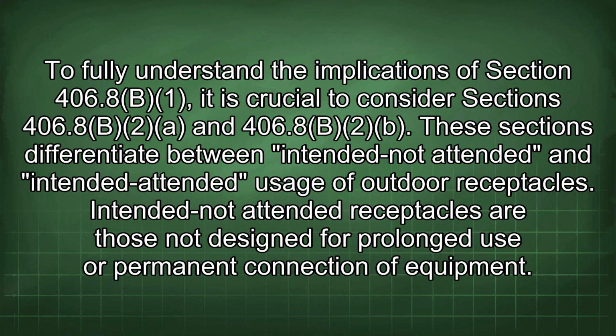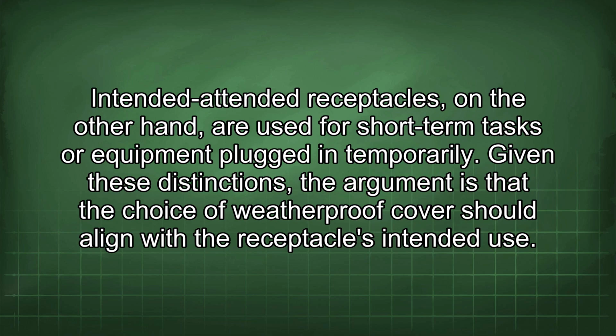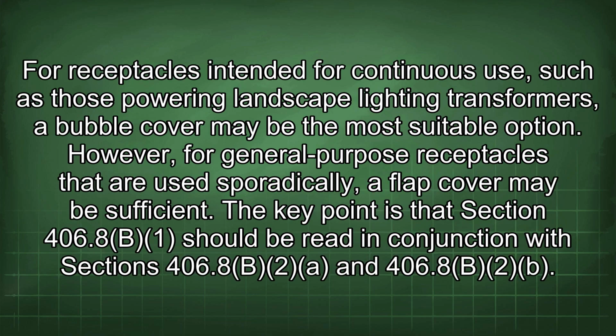To fully understand the implications of Section 406.8, it is crucial to consider Sections 406.8(B)(1) and 406.8(B)(2). These sections differentiate between intended not attended and intended attended usage of outdoor receptacles. Intended not attended receptacles are those not designed for prolonged use or permanent connection of equipment. Intended attended receptacles, on the other hand, are used for short-term tasks or equipment plugged in temporarily. Given these distinctions, the argument is that the choice of weatherproof cover should align with the receptacle's intended use. For receptacles intended for continuous use, such as those powering landscape lighting transformers, a bubble cover may be the most suitable option. However, for general-purpose receptacles that are used sporadically, a flap cover may be sufficient.